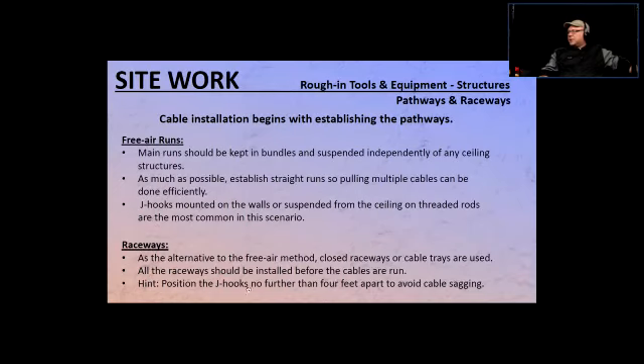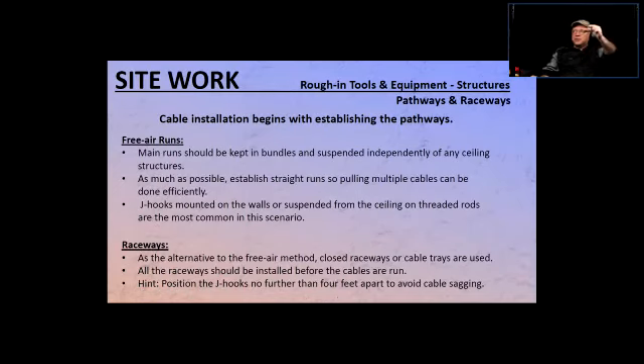Position J-hooks no further than four feet apart in order to avoid sagging of the wires. If you have a big bundle and that bundle sags — basically going in waves between hooks — that's not good because it creates pressure at that point on the wires, especially those on the bottom of the bundle.